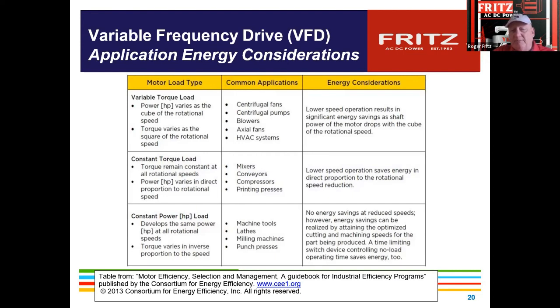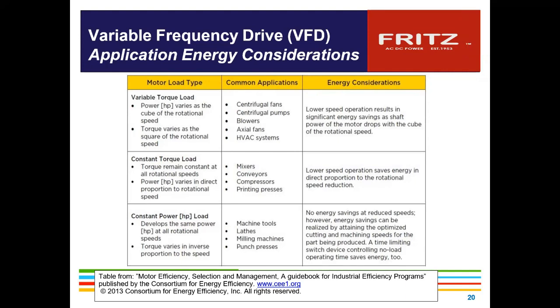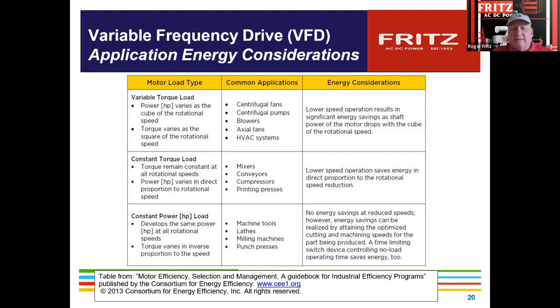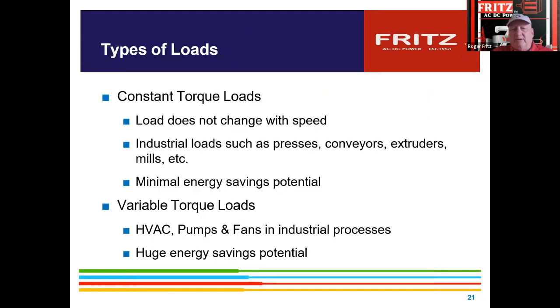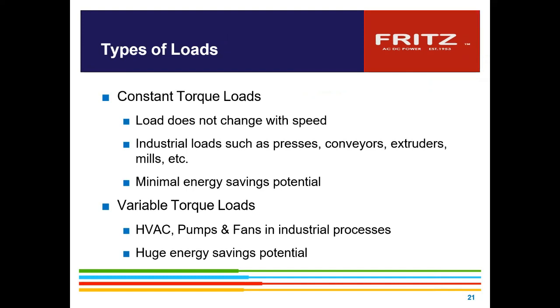But with constant torque loads, by lowering the speed you do get more of a linear savings. And then compressors, it depends on the type of compression it is. Conveyors, it's whether or not you can really slow the conveyor down, let's say to a rock plant or whatever. Printing presses and those things, again, the same thing. There's vacuum pumps and things in there that you need to take a look at. Mixers, we've done a lot of work for various places that had mixing requirements. Again, back to what a constant torque load is, variable.